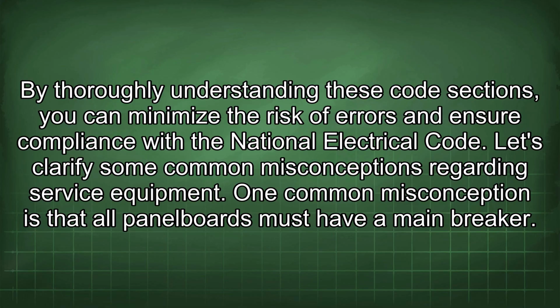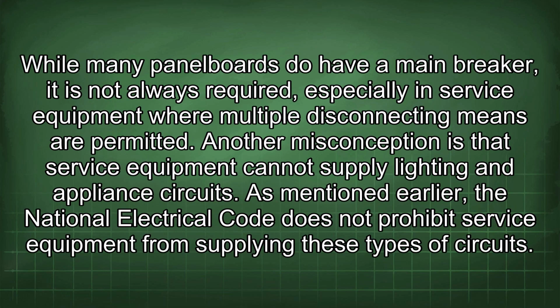Let's clarify some common misconceptions regarding service equipment. One common misconception is that all panel boards must have a main breaker. While many panel boards do have a main breaker, it is not always required, especially in service equipment where multiple disconnecting means are permitted. Another misconception is that service equipment cannot supply lighting and appliance circuits.